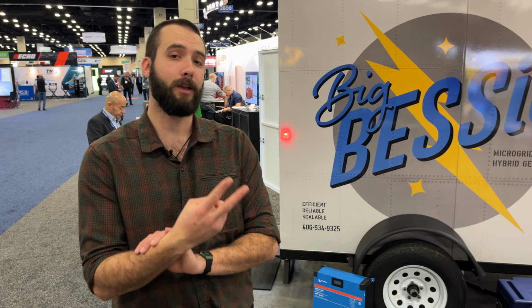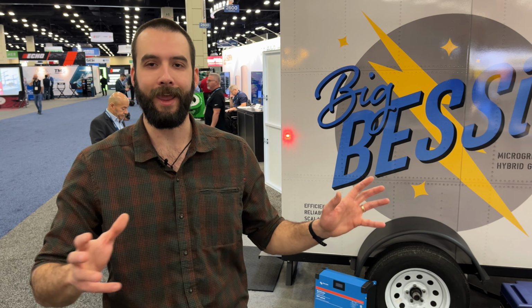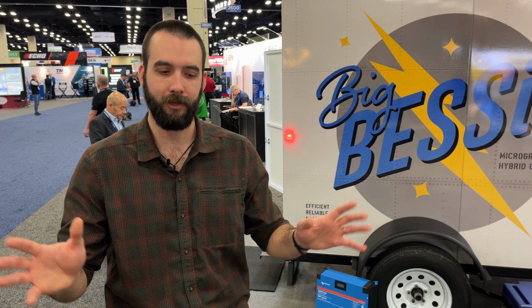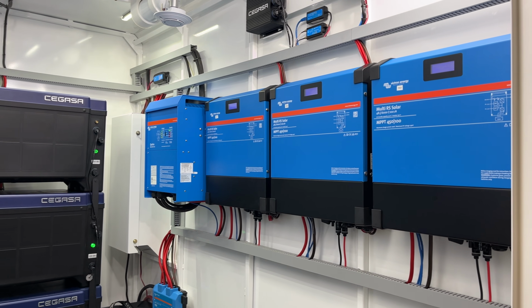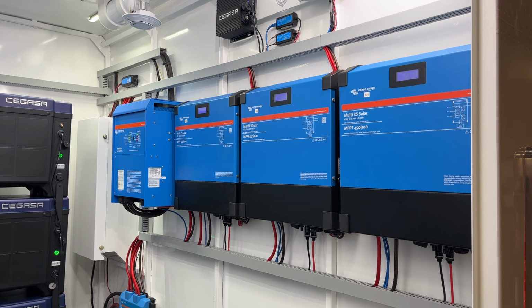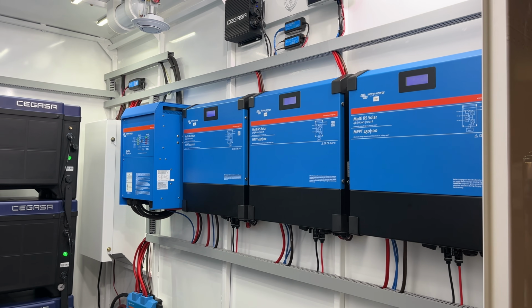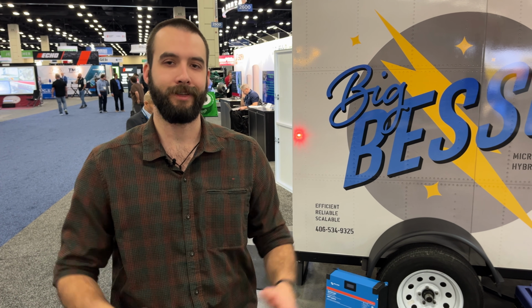Now, there is a second component to this hybrid generator trailer, and that is the ability to hybridize an existing AC gen set. So isolated by the DC bus, we have our AC output and our AC input. Our AC input never sees our AC output. It is simply set up as a battery charger. We have about 15 kVA of onboard charging capability, which would allow us to run that 25 kilowatt gen set that this is set up to replace at its most efficient mode, where we're getting the best gallons per kilowatt hour, we're loading it efficiently.